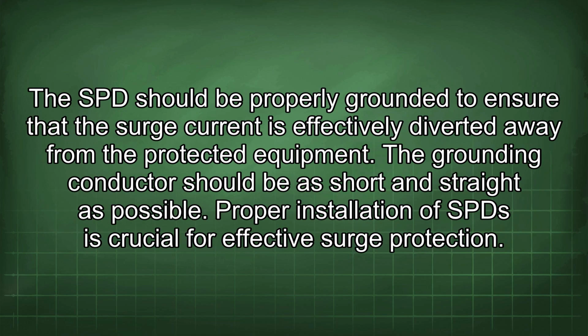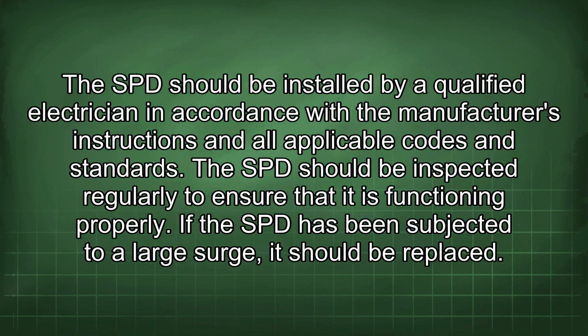The SPD should be properly grounded to ensure that the surge current is effectively diverted away from the protected equipment. The grounding conductor should be as short and straight as possible. Proper installation of SPD is crucial for effective surge protection. The SPD should be installed by a qualified electrician in accordance with the manufacturer's instructions and all applicable codes and standards. The SPD should be inspected regularly to ensure that it is functioning properly. If the SPD has been subjected to a large surge, it should be replaced.